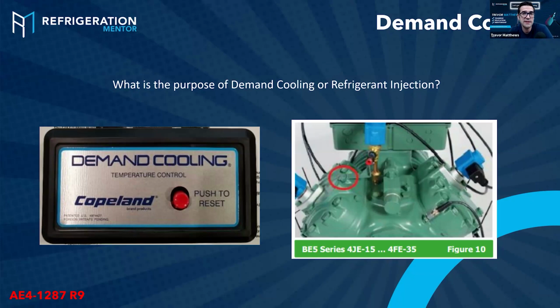What is your SCT or SDT, saturated condensing temperature or saturated discharge temperature? And what is your saturated suction temperature, SST? What is that evaporator running at? What is that condenser running at? That's going to tell you. So those are the design conditions. And the lower you go in temperature, that means lower pressure, which means lower mass flow. So less gas is moving, and all these compressors are refrigerant cooled. We need that mass to come and cool the motor down because the motor generates a lot of heat.